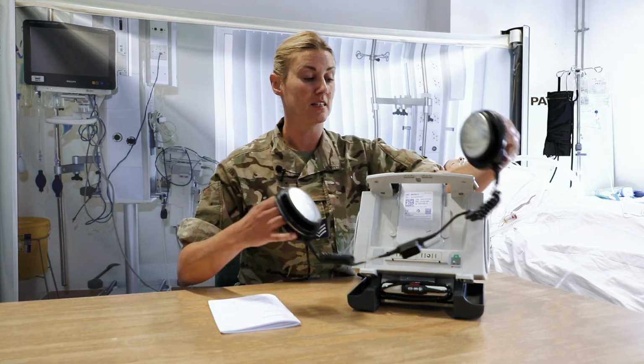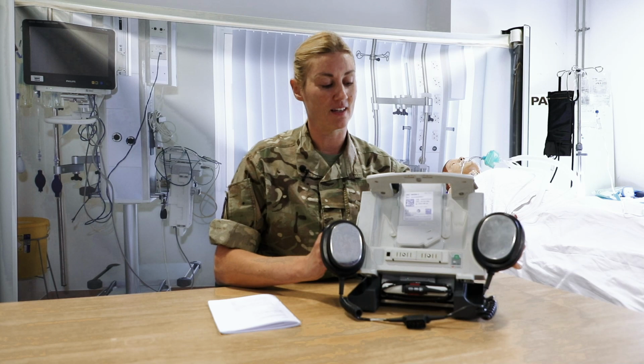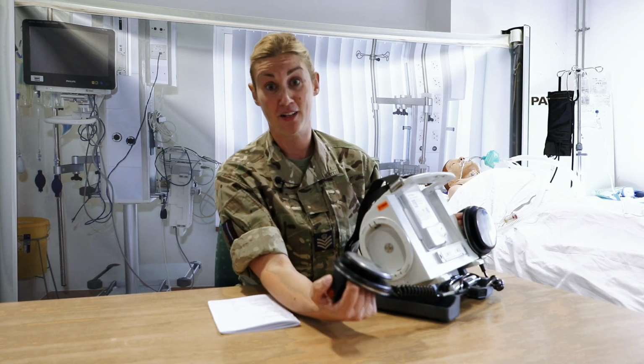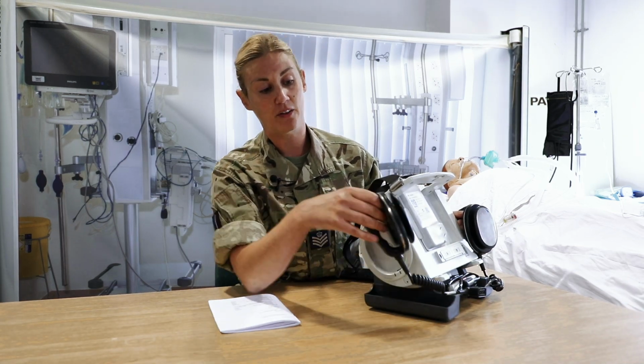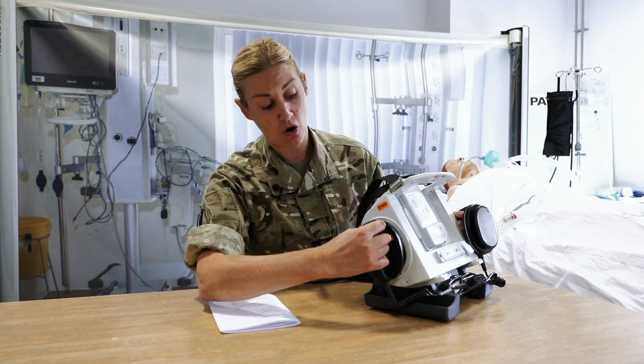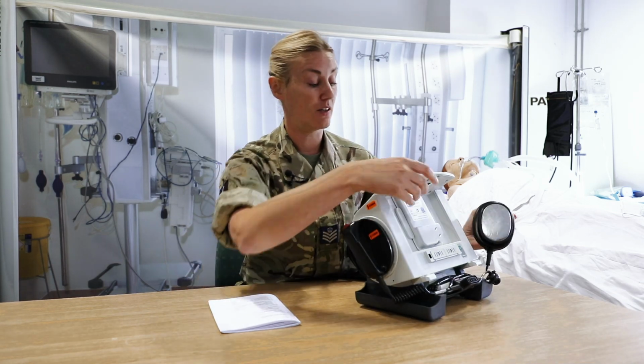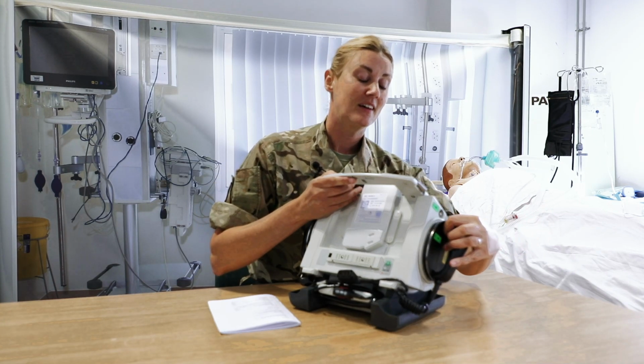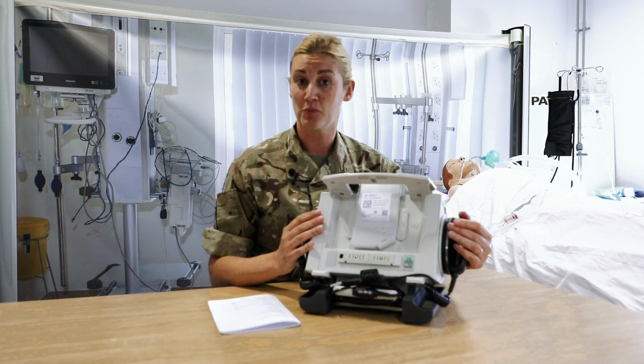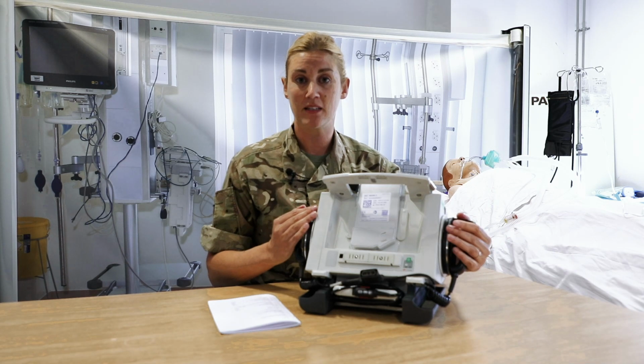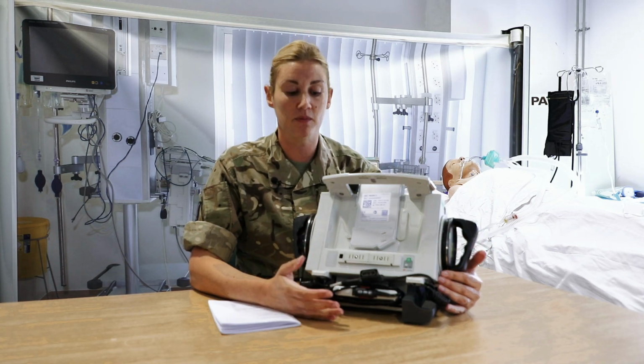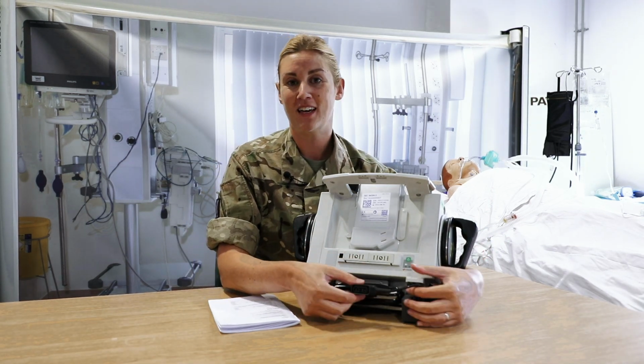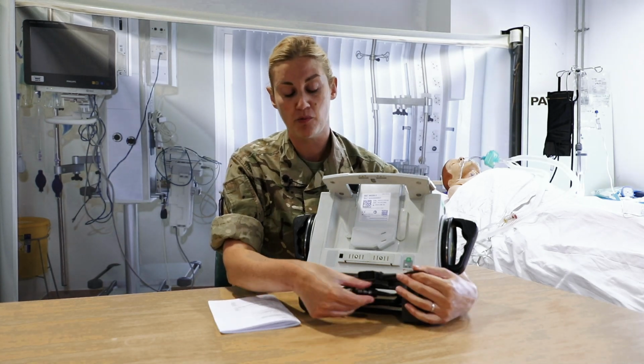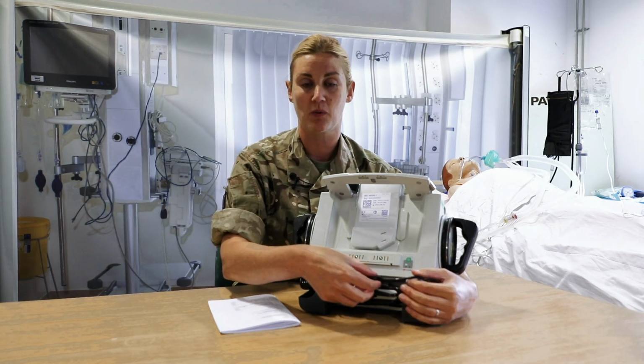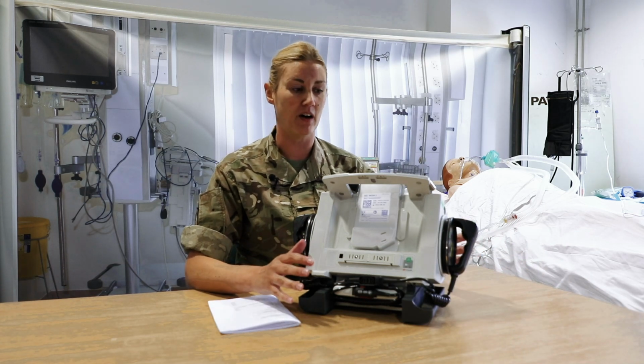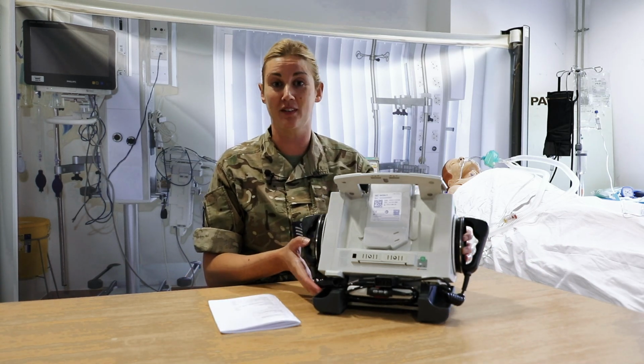This is a biphasic defibrillator, but you'll notice that they are labelled sternum and apex. So you have your sternum orange and your apex green. So they are interchangeable because it's biphasic. You could mix them up. The only advantage of keeping them together like that is it orientates your cable in such a way that if you remove that red master cable and apply it straight away, it's good to go. So it saves a bit of faff, and for those of us who have a bit of OCD, it just looks tidier.